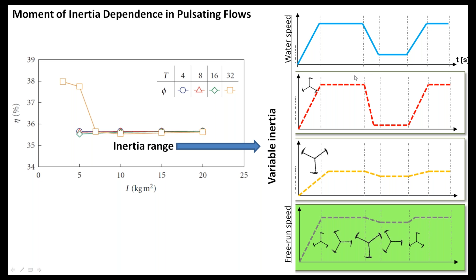We have achieved for the first time with our patent the first passive, fully integrated pitch and inertia variable geometry turbine. So we do not have a family of turbines for a family of power curves — we have only one turbine that can have all the power curves inside it. We can envelop all the power curves to always achieve the best torque, the best power curve, in any variable water flow.